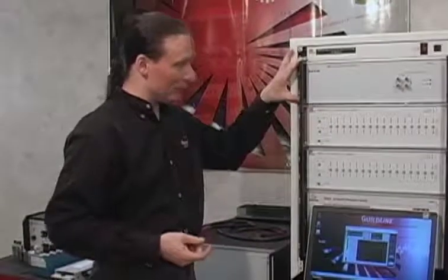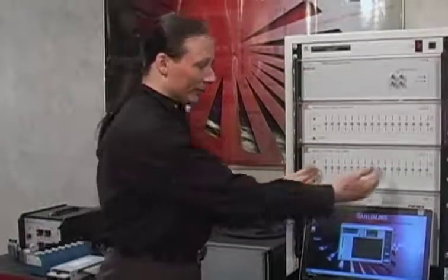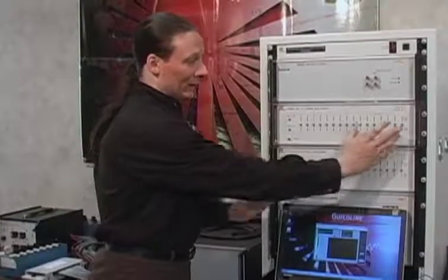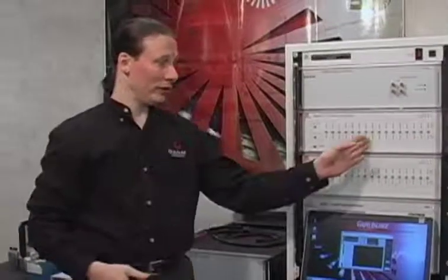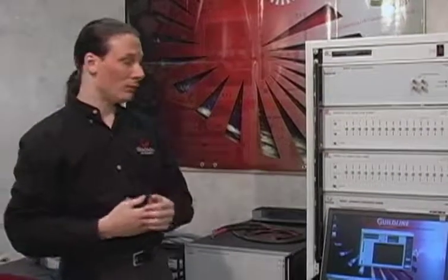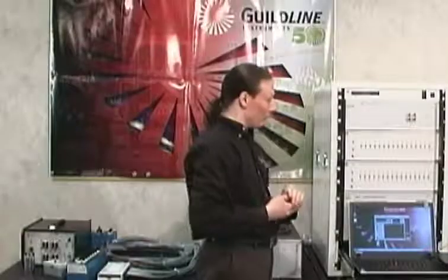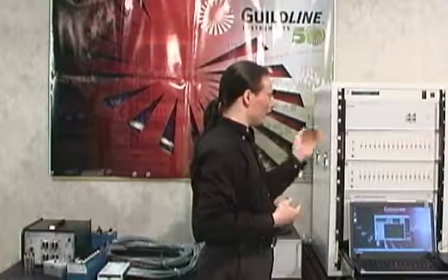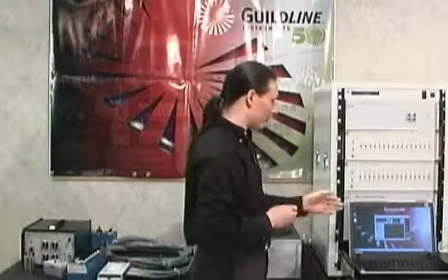and the fact that your resistor bank up here is typically connected to the same channel all the time, from 17 to 25. Your SR1010 is always connected on the first 12 channels, and these are your working channels here, these four here, and from 26 to 32, and these are the devices you would be bringing into the lab to do your calibration work against. Having the semi-fixed configuration allows you to always save templates so you don't have to re-enter all this information over and over again, which is why the file architecture in BridgeWorks becomes very powerful and simplifies a lot of your steps.